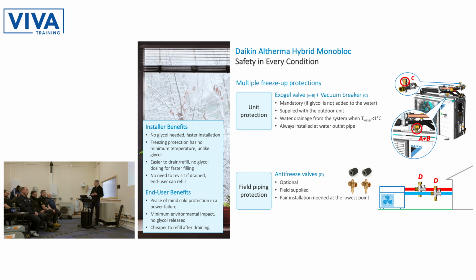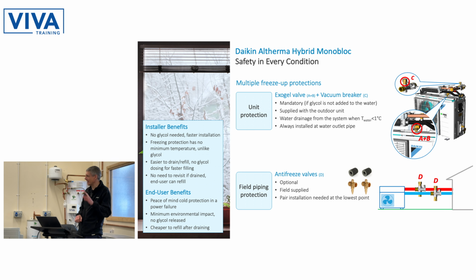If you're installing one in very cold weather, you need to be a little bit careful that the valve doesn't open before you've got some heat into the heating system. That's covered in our training course. If you are replacing a boiler in very cold weather, at -2 or something, then that valve will be open before you've had the chance to fill and warm the heating system. So there are ways around that.